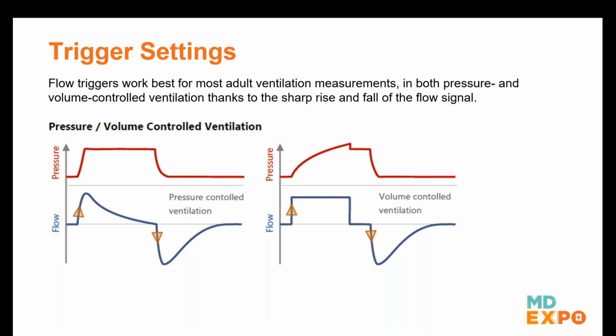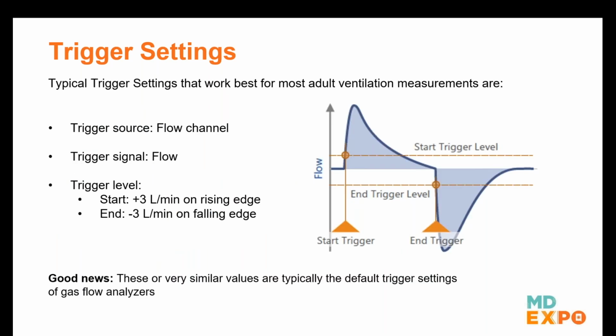Yeah, but again, because this is the case in most or in all the analyzers we've seen out there in the field already, their default trigger settings are, as you can see on this slide, or very close to that. Maybe it is not 3 liters per minute, maybe it's 2 liters per minute, but that doesn't really matter. They all have default trigger settings using the flow curve and a start trigger on a rising edge of, let's say, 2 or 3 liters per minute of flow, and a stop trigger on a falling edge of negative 2 or 3 liters per minute. That works well in almost all the applications where we have a positive and a negative flow through the flow channel.